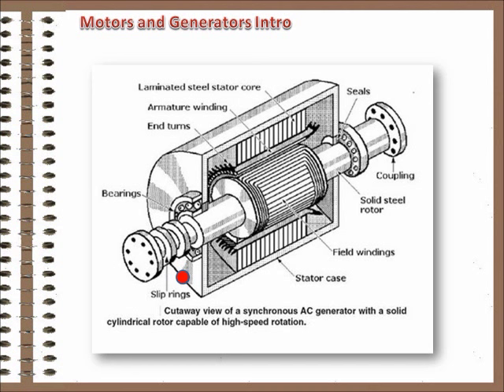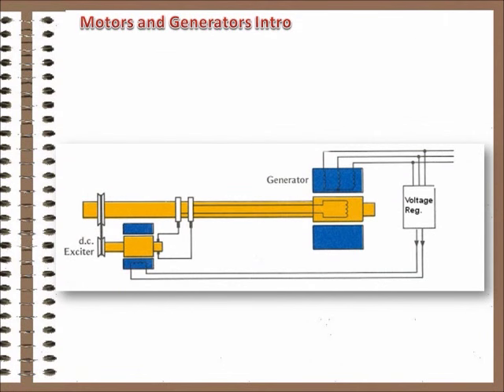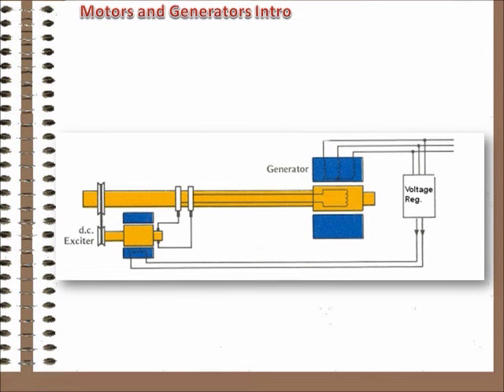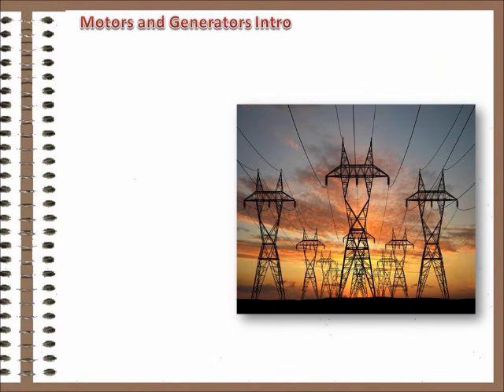Another feature of the AC generator comes from controlling the field. As we said, DC is supplied to the rotor to create the magnetic field that induces voltage in the stator. That DC supply is manipulated by the generator's excitation system to control voltage. Increase current flow to the rotor, and generator voltage increases. The stronger magnetic field induces higher voltage.